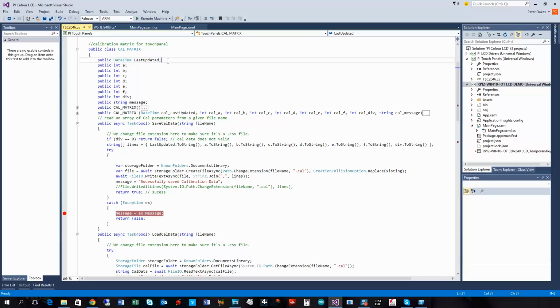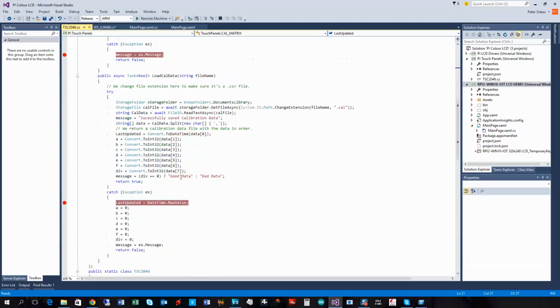If I have an error with it, what I do is I do datetime.max, which is basically 2099.99 or something crazy, 100, 200, 1,000 years in the future or something, so that it's easily identifiable as being an invalid date time for the current calibration data. And then for the load routine, what I do is I go for the same file name, whatever file name it is, ending with .cal. I load it in asynchronously, and then I basically split the line using a comma, because it's basically a CSV single line file, and I then just assign the byte array to each of these different things by using the convert to ints.